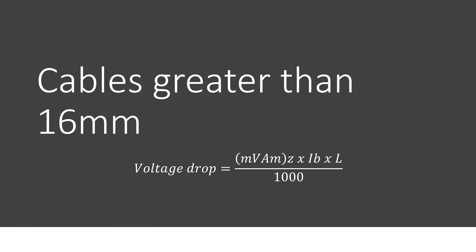Where cables are larger than 16mm and the power factor is known, there is a more accurate method of calculating voltage drop using the resistive and reactive values of millivolts per ampere per meter. This is mentioned in 6.2 of Appendix 4 in BS7671 and I might include this in a future video.